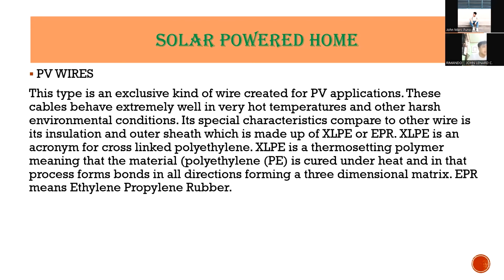So PV wires. This type is an exclusive kind of wire created for PV applications. This cable behaves extremely well in very hot temperatures and other harsh environmental conditions. Its special characteristic compared to other wires is its insulation and outer shell, which is made up of XLPE or EPR. So yung XLPE ay isang acronym for cross-linked polyethylene, and XLPE is a thermosetting polymer, meaning that the material polyethylene (PE) is cured under heat and in that process forms bonds in all directions, forming a three-dimensional matrix. EPR means ethylene propylene rubber.